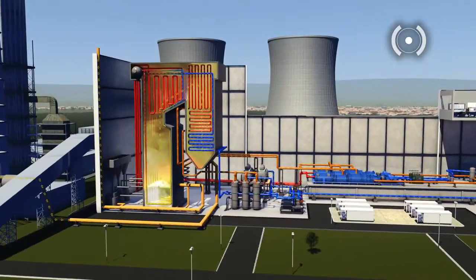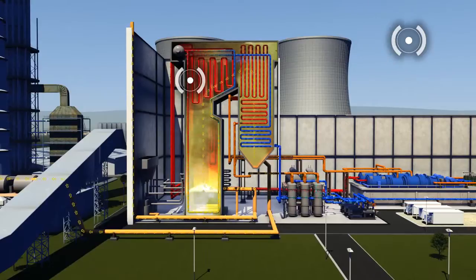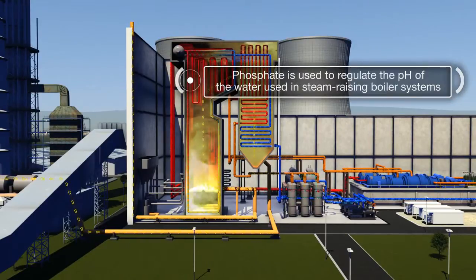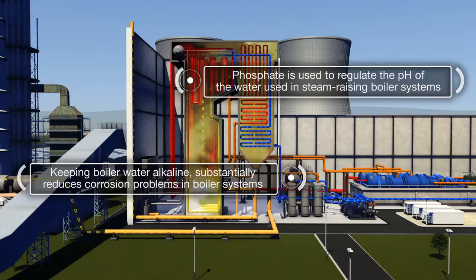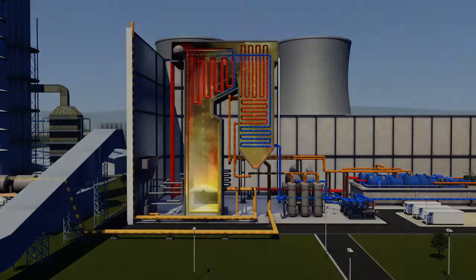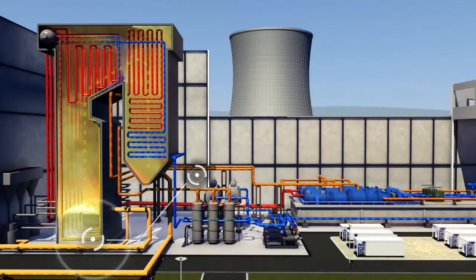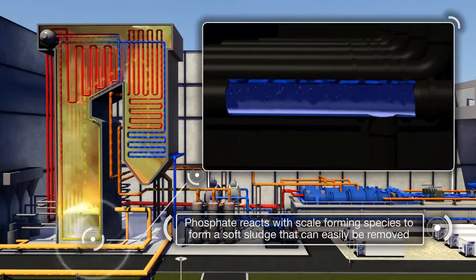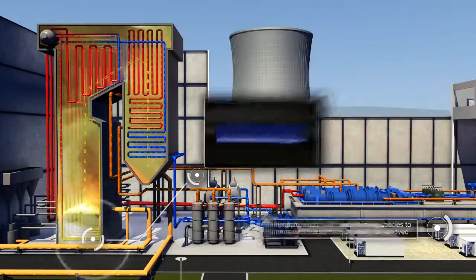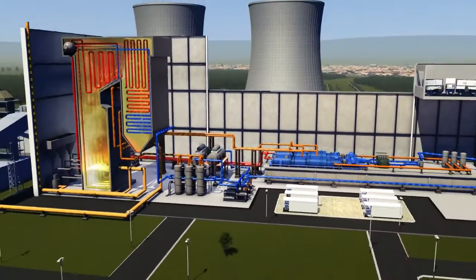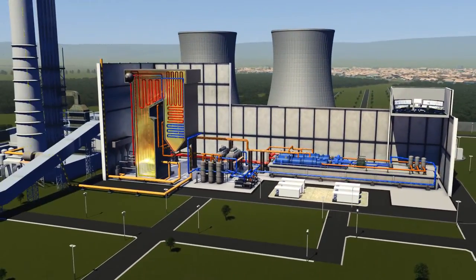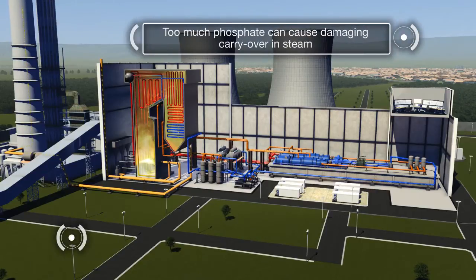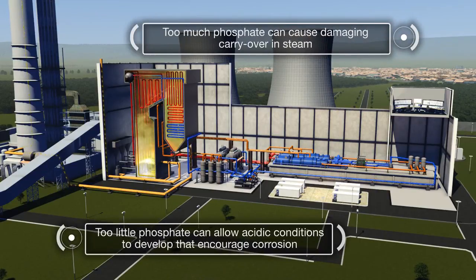Phosphate is measured and used to regulate the pH of the water used in steam-raising boiler systems. Keeping the boiler water alkaline substantially reduces corrosion problems in boiler systems. Phosphate also reacts with scale-forming species such as calcium and magnesium to produce a soft sludge, therefore reducing scaling problems in the boiler and the turbine. Dosing of the phosphate must be controlled carefully: too much phosphate can cause damaging carryover in steam, whilst too little can allow acidic conditions to develop that encourage corrosion.